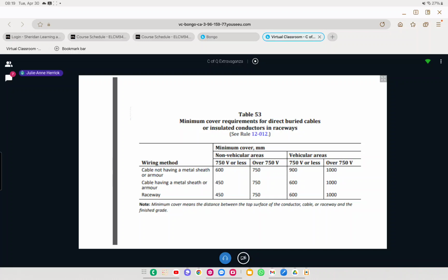You are definitely, absolutely 100% going to get a minimum of one, more likely one, two, three, maybe even four questions based on direct buried cables. So table 53, very important. The question's always going to mention non-vehicular area or vehicular area, or they'll say something like it's a field - clearly non-vehicular - or a driveway, which is clearly vehicular. You're supposed to have some common sense and make that judgment call on your own.